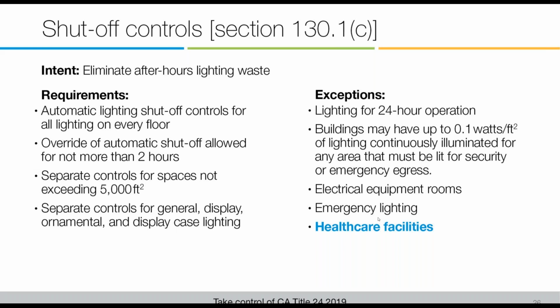A better way to do it, in my opinion, is to add occupancy sensors. It meets the requirement of the code, and it has the benefit of being able to detect whether a person is in the space. So if you've ever experienced that after hours blink warn situation where you have to go up and hit a button, what's actually happening there is the lighting control system is attempting to use programming to determine whether or not a person is in the space. So it flashes the lights, the person gets up and presses a button, and that lets the lighting control system know that someone is still there. That's a pretty complicated way to do something like detecting a person when you have devices that are available to do that. They're purpose-built for it, like an occupancy sensor, which is actually designed to do just that.